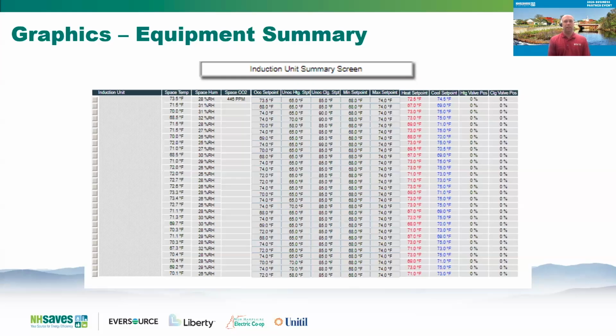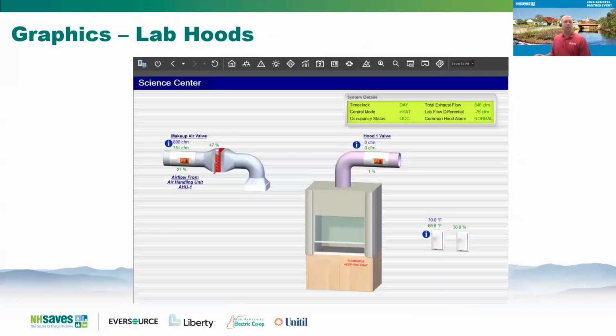individual floor plan. So, for example, you can see, in the middle of winter, are you doing a ton of reheating? And more importantly, in the middle of the summer, are you doing a ton of cooling and then reheating? Allows you to get a glimpse of what's going on very quickly. So, strongly recommend encouraging those to be included in projects, not only from an energy standpoint, but from an operations and maintenance standpoint. Here's an example of a lab hood, so just another system type.